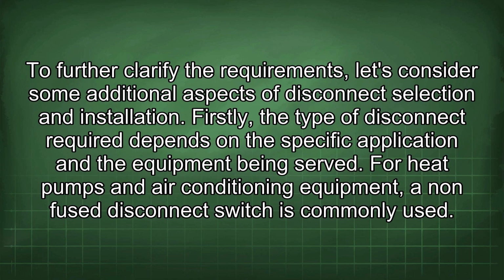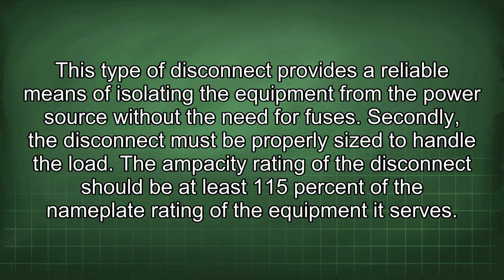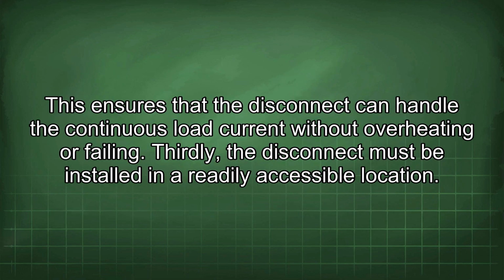To further clarify the requirements, let's consider some additional aspects of disconnect selection and installation. Firstly, the type of disconnect required depends on the specific application and the equipment being served. For heat pumps and air conditioning equipment, a non-fused disconnect switch is commonly used. This type of disconnect provides a reliable means of isolating the equipment from the power source without the need for fuses. Secondly, the disconnect must be properly sized to handle the load. The ampacity rating of the disconnect should be at least 115% of the nameplate rating of the equipment it serves. This ensures that the disconnect can handle the continuous load current without overheating or failing.